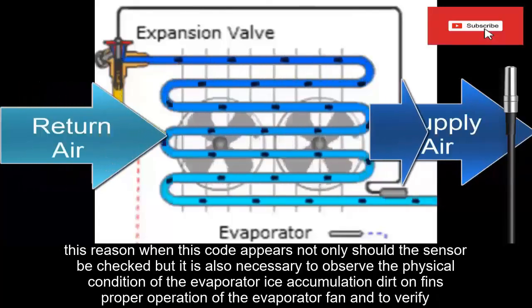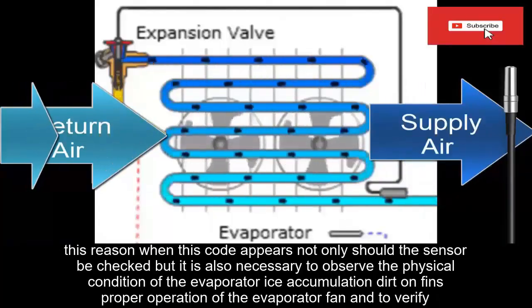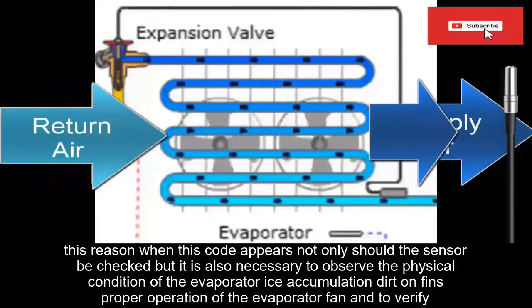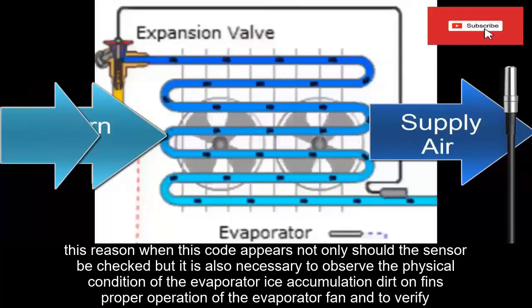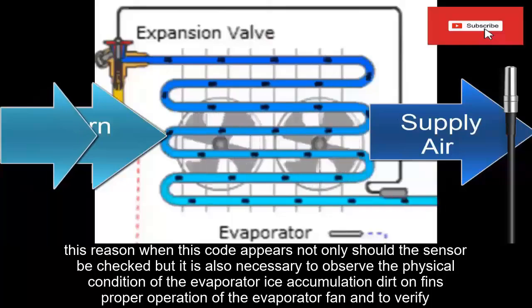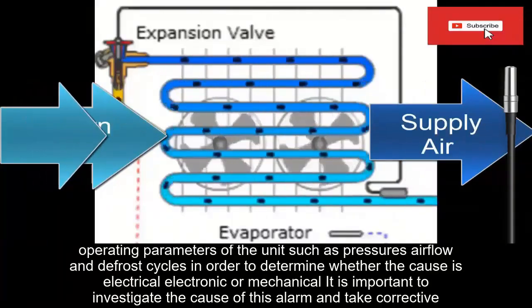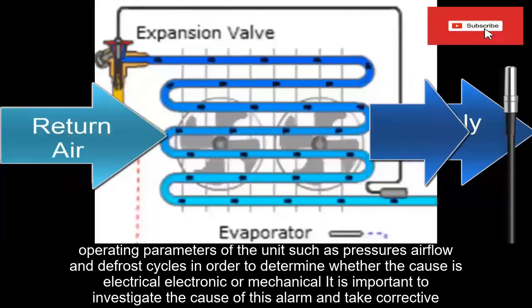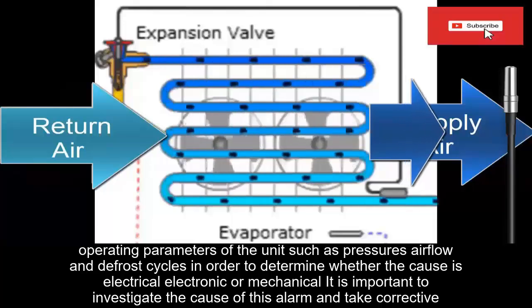For this reason, when this code appears, not only should the sensor be checked, but it is also necessary to observe the physical condition of the evaporator, ice accumulation, dirt on fins, proper operation of the evaporator fan, and to verify operating parameters of the unit such as pressures, airflow, and defrost cycles in order to determine whether the cause is electrical, electronic, or mechanical.